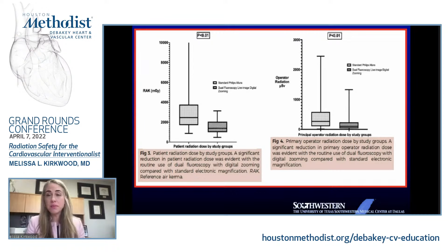So some important principles to remember. Dose rate at the image receptor is maintained at a constant level to preserve image quality. So that compensates for variations in patient size or attenuation. So if you have a very large patient, your table is going to be lower. Your image receptor is going to be further from your X-ray tube. So it's going to have a feedback loop that tells your X-ray tube to increase the radiation dose.